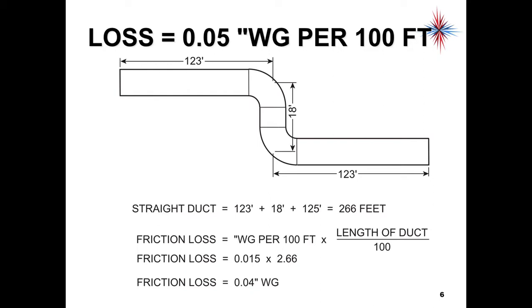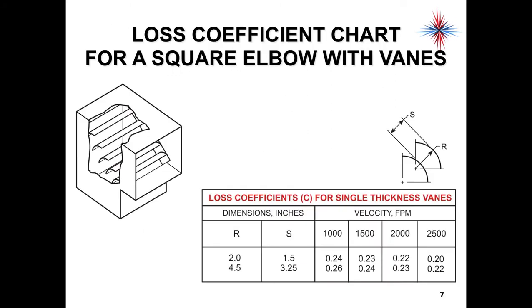Okay, sort of makes sense. We never round down on friction loss, always round up. Now, most of the pressure loss in fittings comes from the dynamic loss. I have a handout online at training.christophermolnar.com that will show you what the dynamic loss is. But for now, let's look at this table.